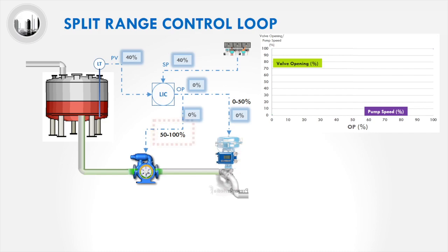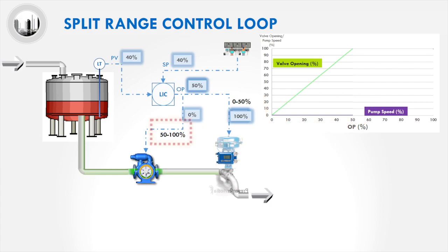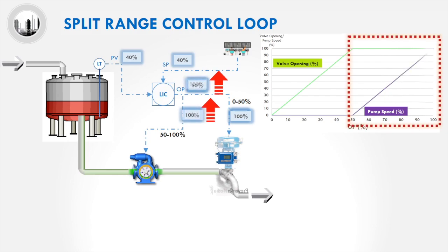To understand how split range control works, let us assume the controller output increases to 50%. At a controller output value of 50%, the valve opening is at 100%. However, the pump speed will remain at 0%. The pump speed does not increase because the split range control will only increase the pump speed when the controller output is above 50%. When the controller output is above 50%, the pump speed slowly increases to 100%.